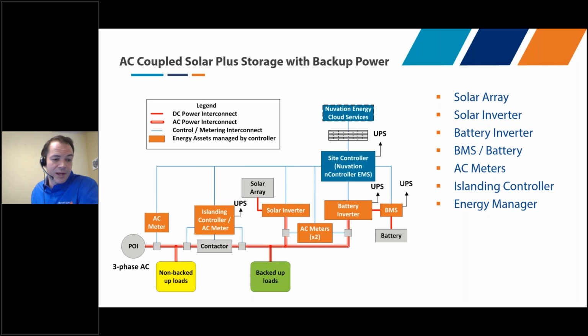We also wanted to talk about backup power and how AC coupled and DC coupled can differ in those applications. This is a block diagram showing an AC coupled system of solar plus storage with backup power. On the bottom left we've got three-phase AC power, then a yellow box of non-backed up loads, followed by a contactor which provides islanding capability. In the event of loss of grid power, that islanding contactor opens, and you're still left with your green backed up loads being provided for out of the solar array and the battery behind the system.